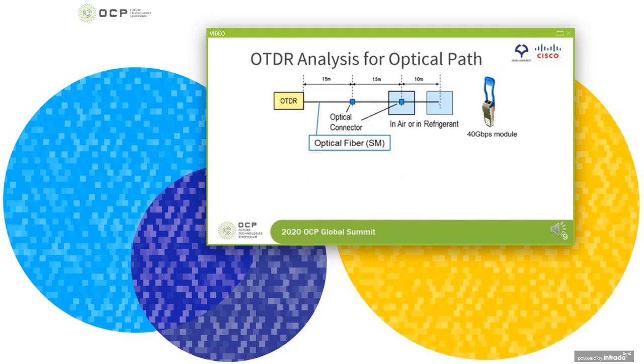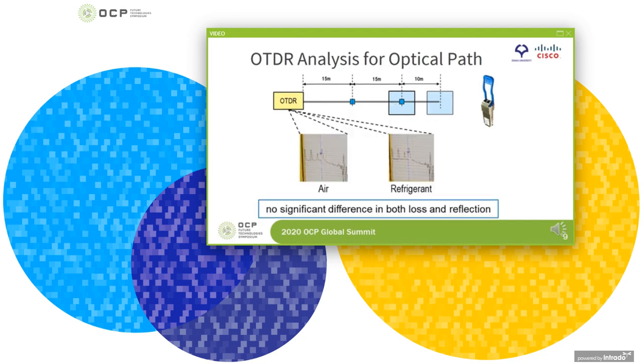To investigate the communication breakdown, we checked the optical path of optical fibers connected to the 40 gigabit per second module, placed in refrigerant and also in air. For this, we used OTDR analysis. An almost identical OTDR trace was observed when immersed in refrigerant and when operated in air without immersion. This result indicates that immersion of the module has no effect on optical coupling.